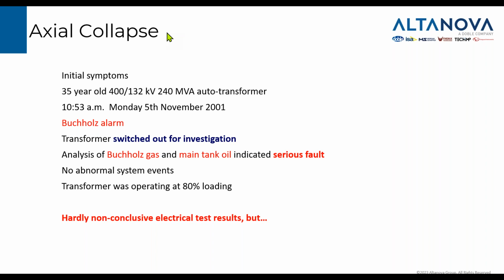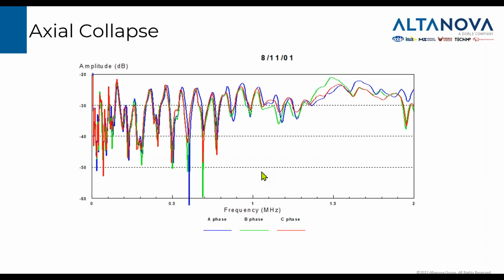Analysis of Buchholz gas and main tank oil indicated a serious fault, so we knew something happened inside. No abnormal system events were noted apart from that, and the transformer was operating at 80% of loading at the moment when it failed. We did electrical tests on this transformer. There was hardly anything conclusive from all the electrical tests. The only thing which we saw was this.